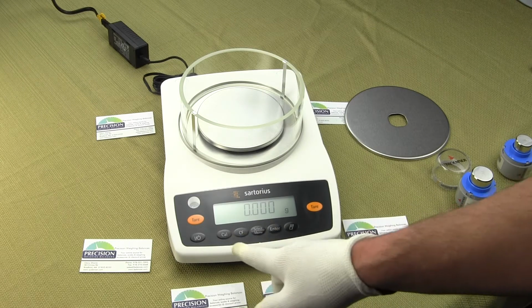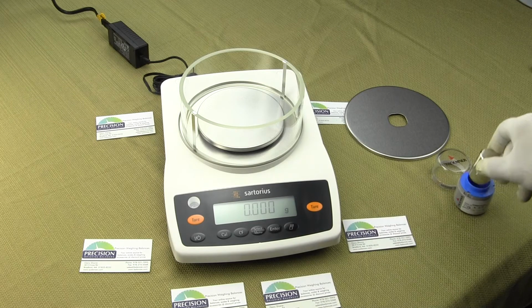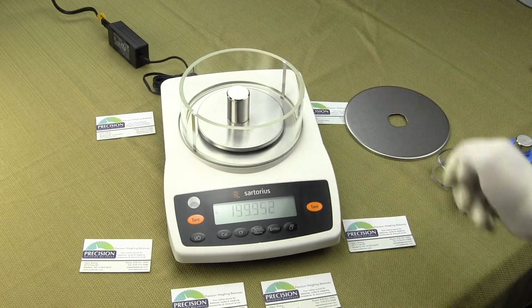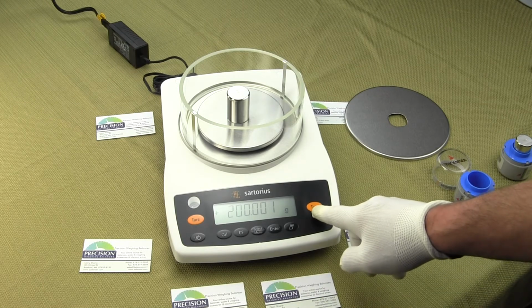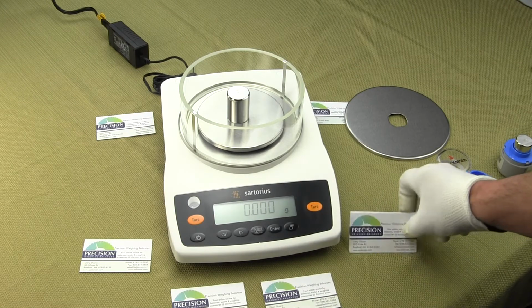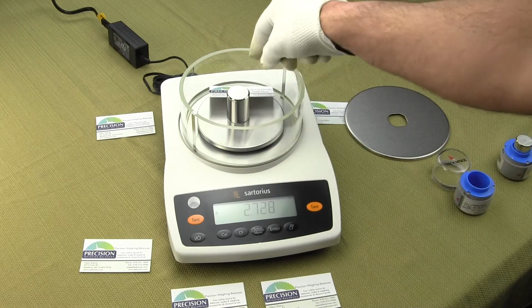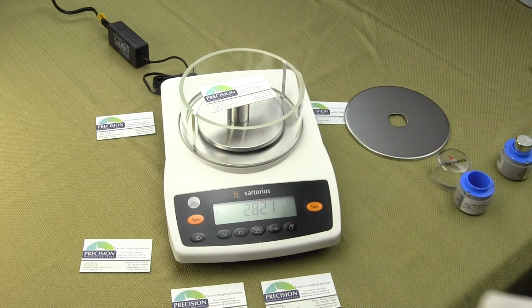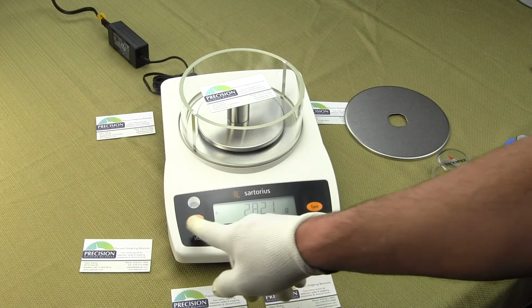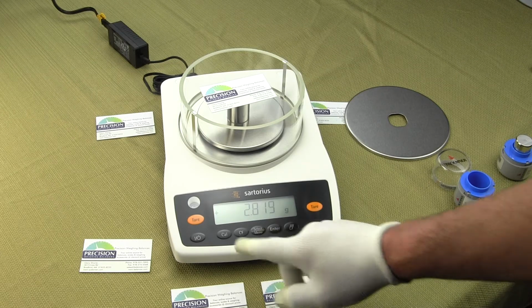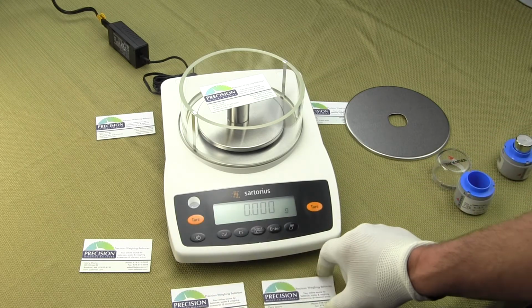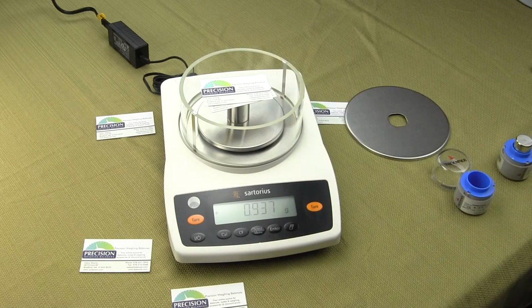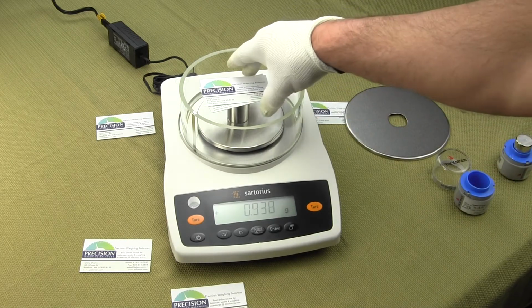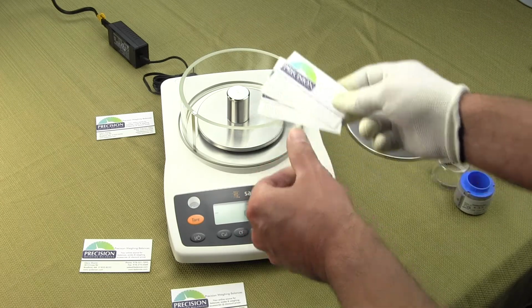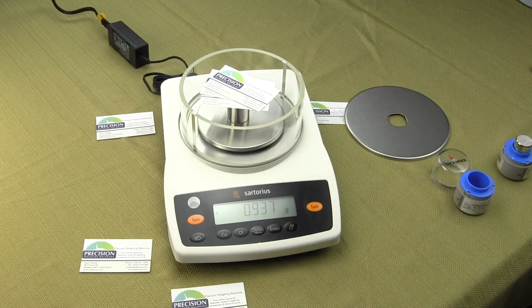So in regards to the keypads here, we have two tare buttons. So if I put a calibration weight on, we'll just say we want to tare it. We could hit the tare button, it would zero it out. Then we could place, we'll say, a business card on there, and it would tell us the weight, and we could tare it again. Now you can tare it from either the right or the left. So this time we'll try the left. You can tare it out. You put another one on. So you can see how quick, and I believe there were 2 business cards on the bottom, so there's 3 there now. You can see how fast the balance is and how stable the weighing results are.